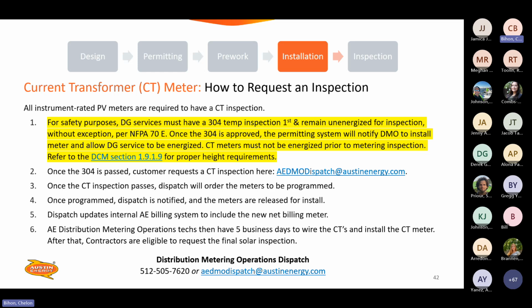So on CT services, we do need them unenergized. We ask that you request the 304 temp before your shutdown date or before your tie-in date, at any point before that during the normal day, so that we can do a full inspection before it's energized, to make sure that everything's safe to be energized. Then if you're doing a supply tap or a shutdown, you're going to have a later date on that CT inspection during the shutdown also. That is separate from our inspection. You will need to have a CT inspection. CT inspections happen before it's energized, as well as the 304 temp.